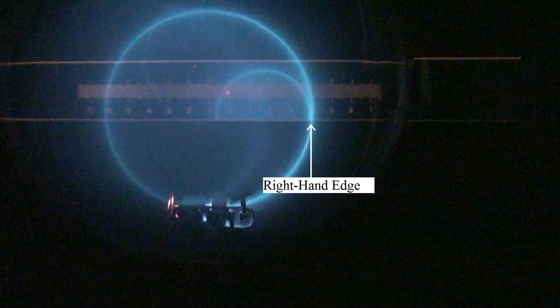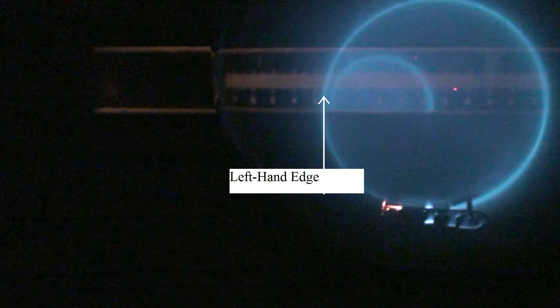Compare the right edge of the beam with the scale by moving your eye until the mirrored beam matches the actual beam at the right-hand edge. This ensures that you're looking squarely at the beam. Now move your eye to the left to match the left edges and take another reading. The diameter is now determined.